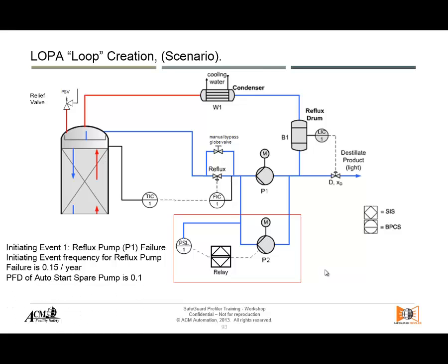failing closed. So I could also use another safeguard as long as it is independent from the basic process control system that is working and interacting in order to keep all the parameters inside the intended design operating envelope.